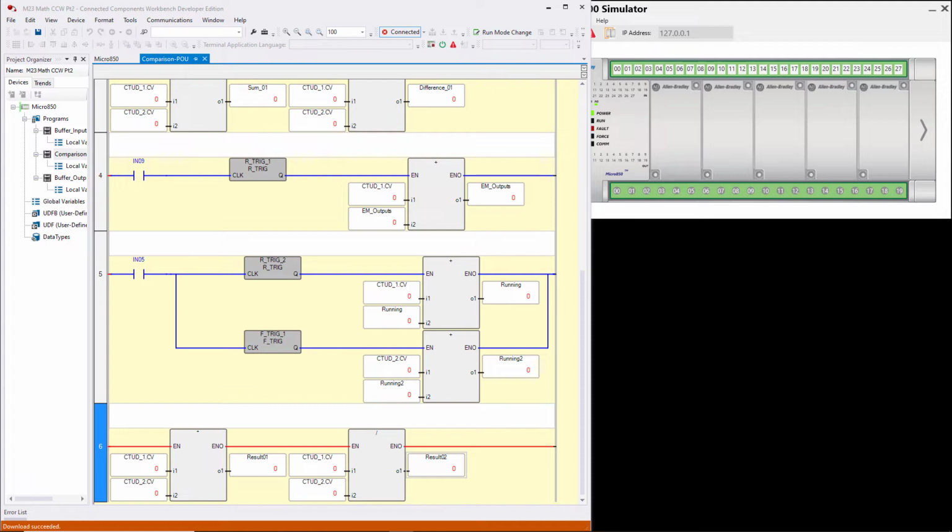So the first instruction, I'm multiplying 0 times 0, the result is 0. In the second instruction, I'm dividing 0 by 0, and the result is 0. You'll never get in trouble with multiplication, not unless you accidentally drive an overflow. In other words, if you're using double integers, there is a maximum value. If you multiply the maximum value of a double integer times the maximum value of a double integer, the result is going to be larger than a double integer. There's where you could get in trouble with an overflow.